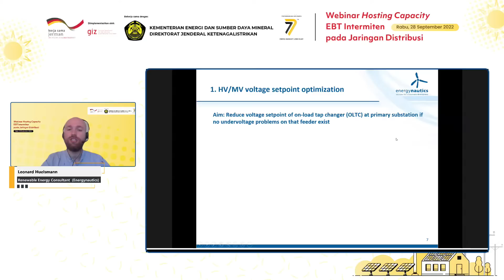One possible way to improve voltage issues in distribution networks is that you can reduce the voltage set point of your primary substation transformer, if that works for you. So here's a quick illustration of this. You may have a certain distribution feeder with hundreds of customers connected, with distribution lines running up to about 5 kilometers in length. During the situation of peak load, we will see a voltage drop across this distribution feeder.